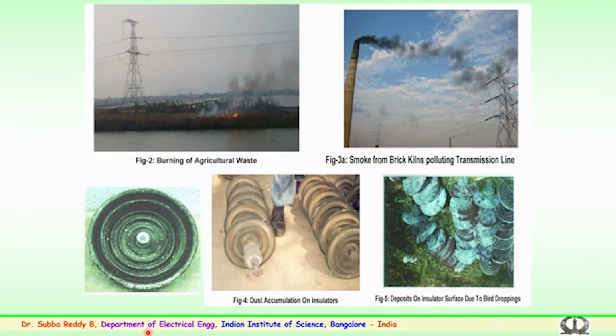So, these are again the various types of accumulation of dust on the surface of insulators. Again, this is the bird droppings over a period of time. Many times you must have noticed that on the transmission tower several huge birds make their nests, and the droppings of that will settle and pollute the insulator. The insulator gets polluted over a period of time, and will lose its properties, and in case of wetness the entire surface starts conducting and the flashover is likely to happen.